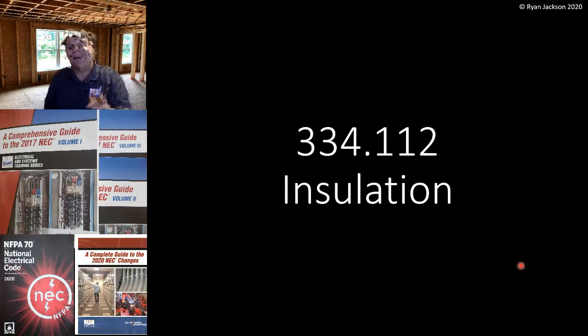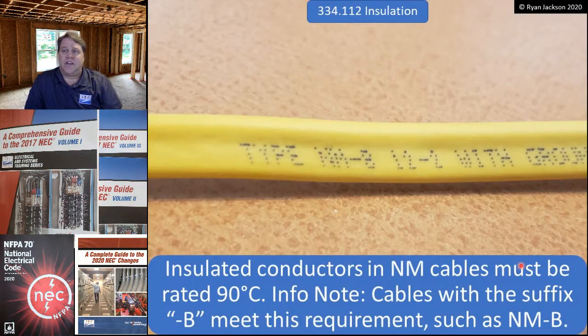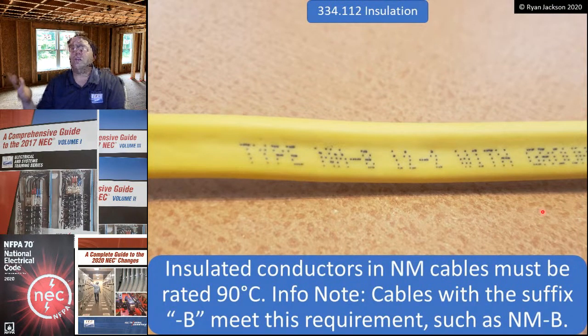And then the last thing that we're going to cover tonight is 334.112 insulation, which we kind of already talked about. Insulated conductors in type NM cables must be rated 90 degrees C. Not an option. You cannot manufacture NM cable that's only rated 60 or 75. And then we have a useful informational note here that says cables with the suffix -B, NMB, meet this requirement. So if I have NMB, then I know that is a 90 degree conductor.